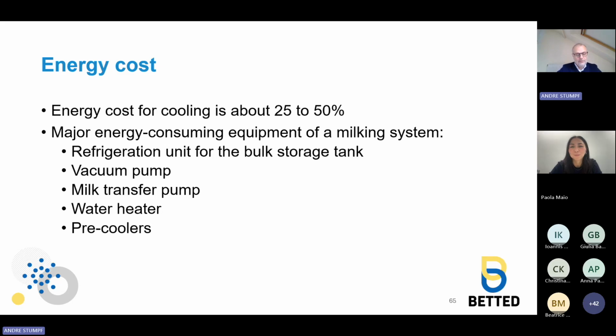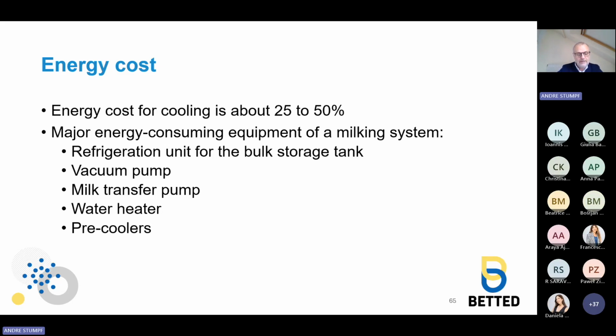Okay, so if you focus on the energy cost, in a typical dairy plant in the EU, the cold production often accounts for between 25% and 50% of total energy consumption cost. It is therefore essential to reduce energy consumption. Milk cooling and systems for washing make up the largest part of the electricity used by dairy farms. With the latest technology improvements, there are generally gains to be made in energy efficiency. The main considerations for improving energy efficiency include new technology, upgrading older, less efficient equipment, and improving maintenance practices.